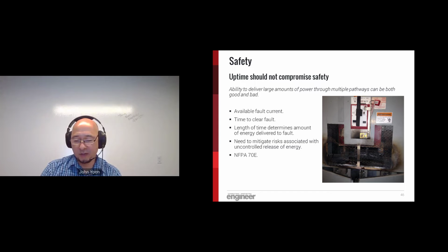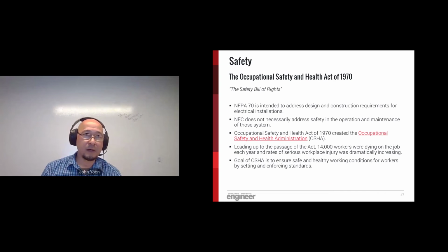We constantly talk about reliability and uptime to make sure that we have more than enough capacity to serve current and future loads. But in the same breath, if something bad happens, we have to have certain design and operation principles and practices. This is where OSHA and NFPA 70E come in. Although the NEC is not a design manual, it does contain prescriptive practices regarding how distribution systems are designed and installed. You know, things like service clearances that Jeff will talk about later and some other constraints. However, the NEC is not intended to tell you how to operate that equipment in a safe manner after it is installed. So why is that a concern?